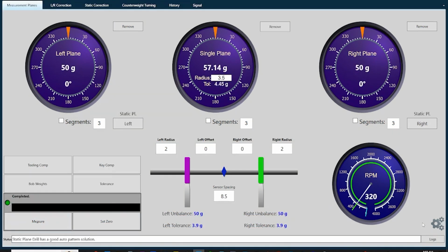Once you are satisfied with the calibration numbers, open the settings page once more and click the checkbox below the calibration speeds that says Select by RPM. This setting enables the software to automatically select the closest calibration speed when you choose to take a fresh reading.